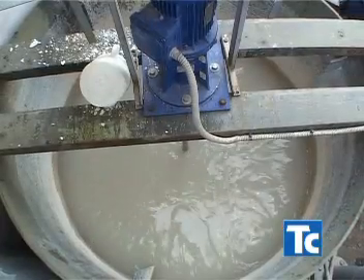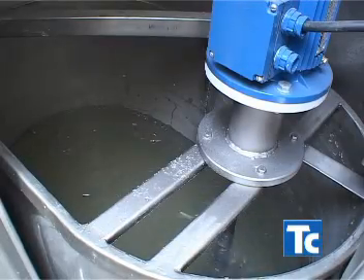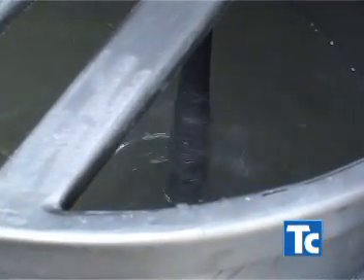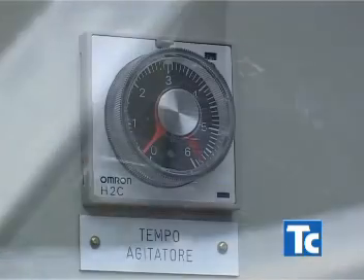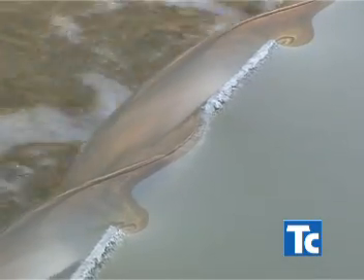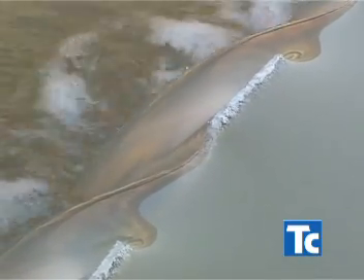The purpose of the flocculating pump is that of injecting a chemical product which, once dosed in the right quantity, has the primary effect of separating the working dust from the water by turning the foam into heavy flakes. The chemical product is diluted to a percentage of 1 per 1000 into a container where it gets adequately mixed. In this way the heavy flakes settle fast at the base of the cone. By adequately controlling the flocculating pump, it is possible to get almost clear water.